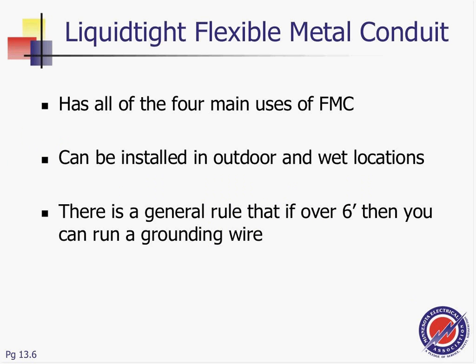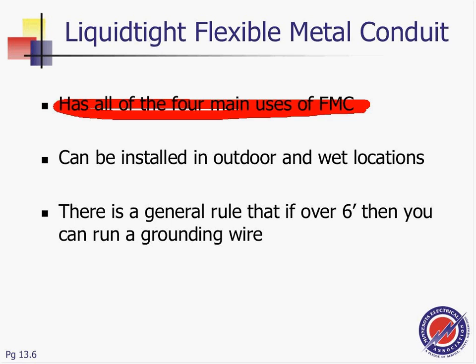So it's a flexible metallic conduit. What did they do? They added a Liquidtight cover, some type of non-metallic cover. So all of the main uses of flexible metallic conduit, you can use it anywhere. You can use it to tie to a lighting fixture. Use it in a wet location, dry location, damp location, no problem. Tie to equipment, tie to fixture, fish in the wall. So you can basically use it for any place that flexible metallic conduit has been used.